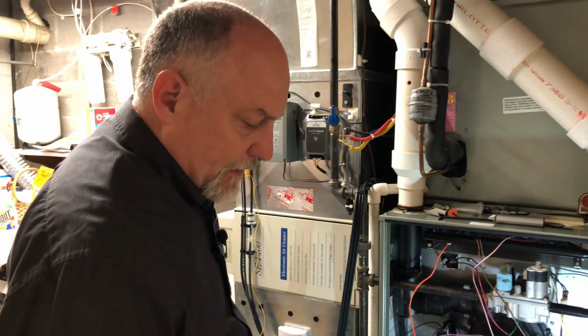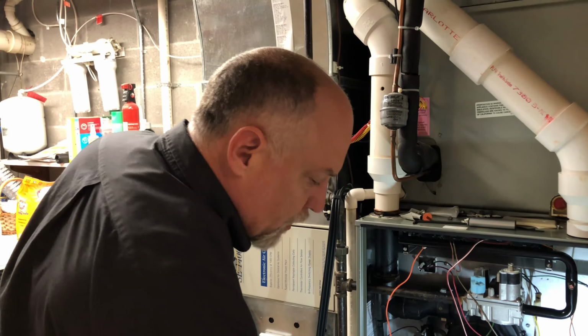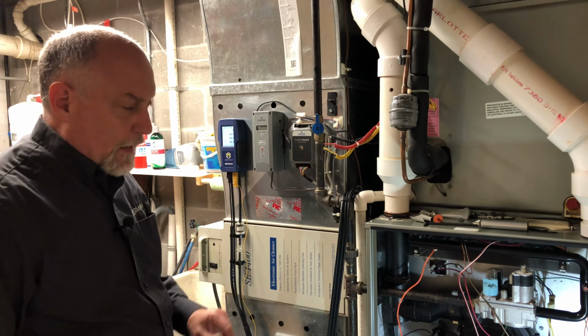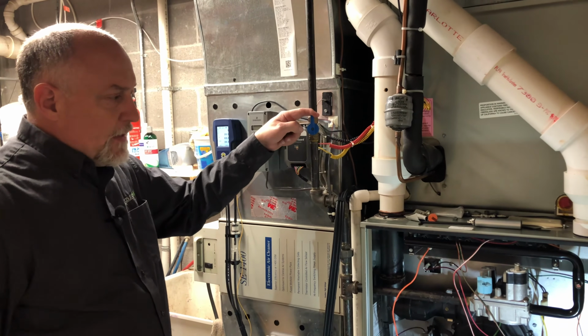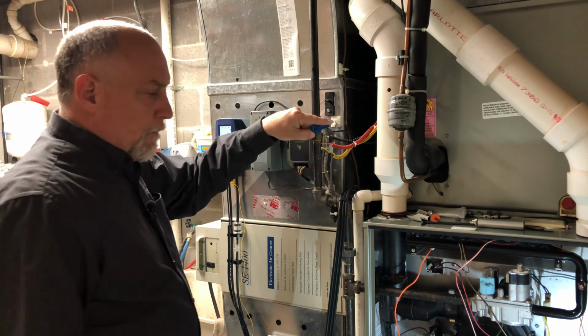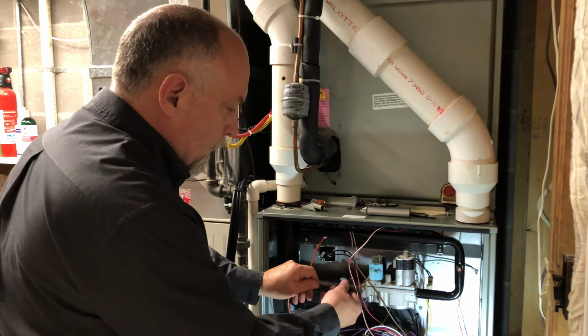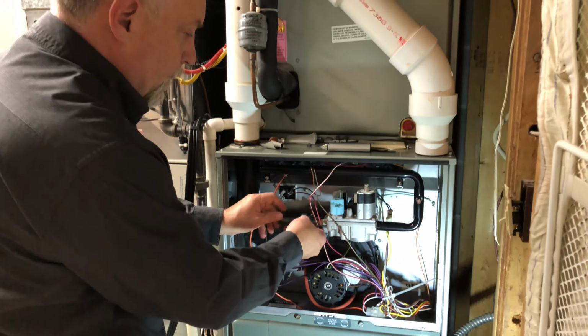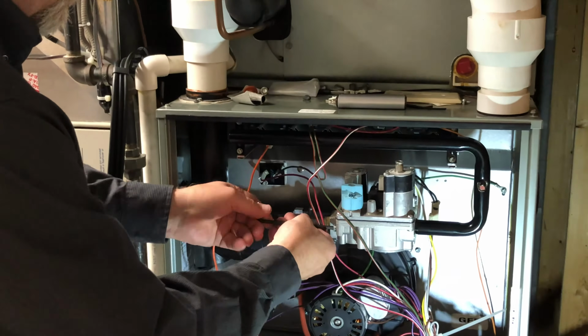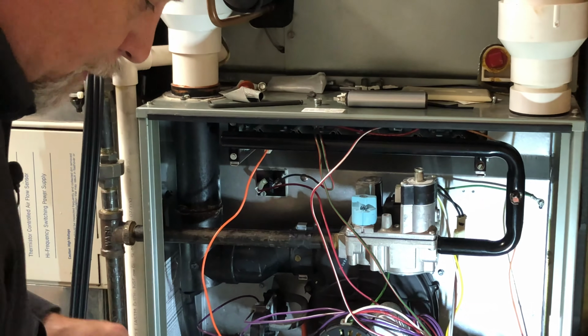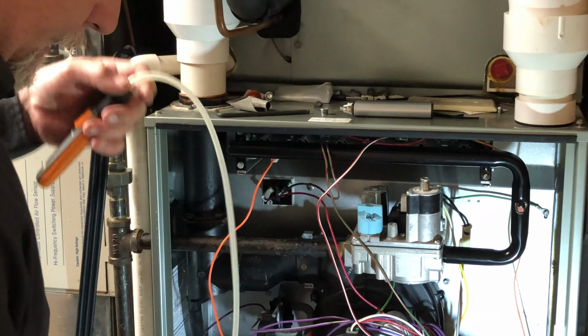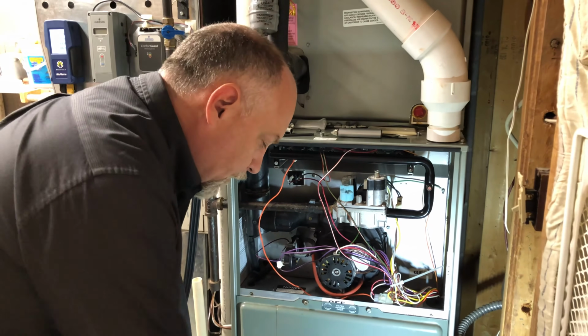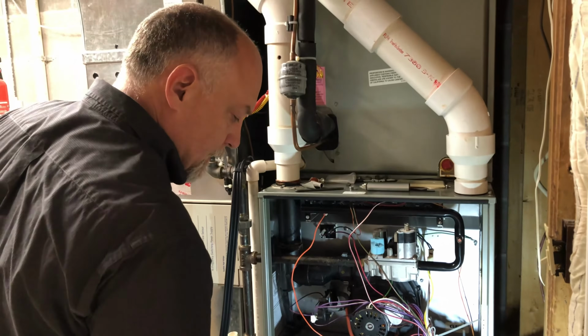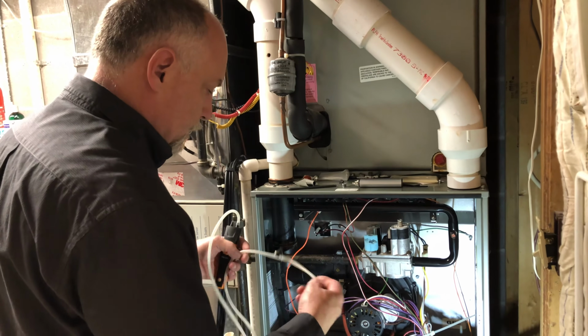So now that we got the gas leak detection done, and we made sure there's nothing wrong with the furnace, we're going to actually hook up the manometers. So I'm going to shut the gas off here because I'm going to hook up to the incoming gas pressure. So I'm going to go ahead and back the incoming plug out. And again, you've got to have the gas pressure off on this one, because this one here is for my pressure switch. And this will be the incoming gas pressure.